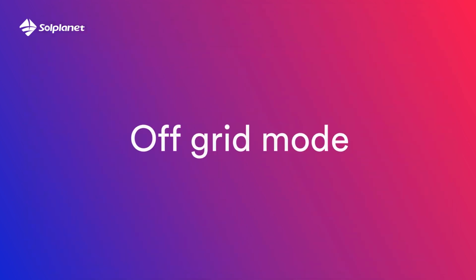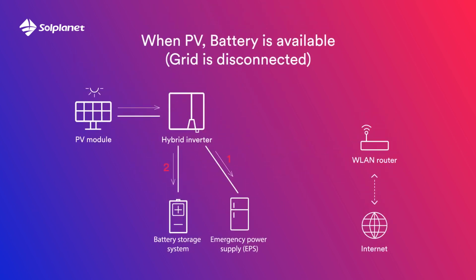Off-grid mode. When PV and battery are available, grid is disconnected. Solar energy provides power to the loads as first priority. If solar energy is sufficient to power all connected loads, solar energy will also charge the battery. If solar energy is not sufficient to power all connected loads, battery energy and solar energy will supply power to the loads at the same time.